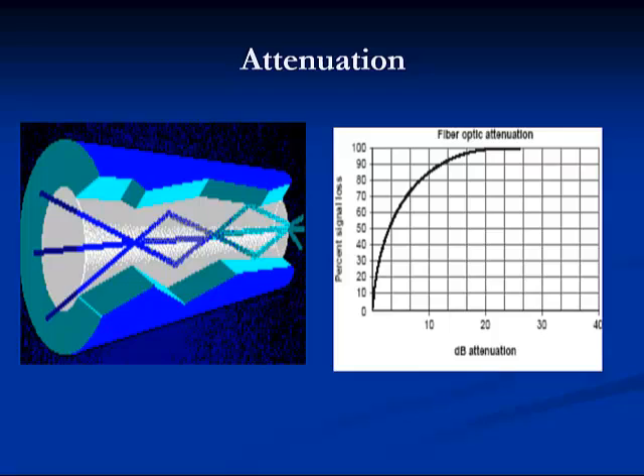Many different problems can cause attenuation of a light signal in optical fiber, including excessive gap between fibers in a connection, improperly installed connectors, impurities in the fiber, excessive bending of the cable, excessive stretching of the cable, and dirt on the connector itself.